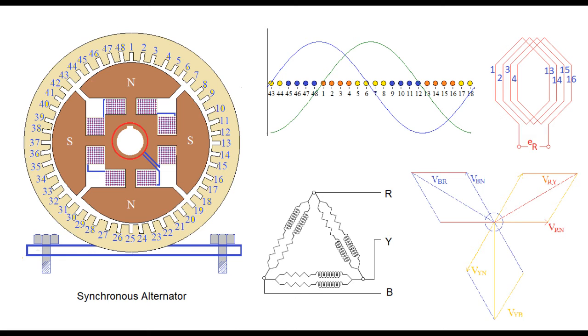We may keep these phasors separate or connect them in star or delta. If those are connected in star, we may check that line voltage is √3 times phase voltage. If the windings are connected in delta, the closed delta circuit may be checked for zero current, since voltages are equal and balanced. This is the open circuit condition in both star and delta connections.